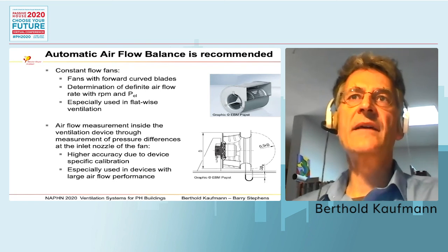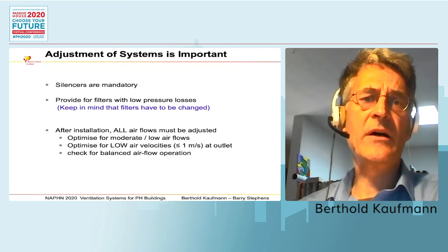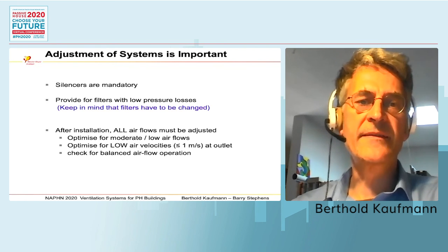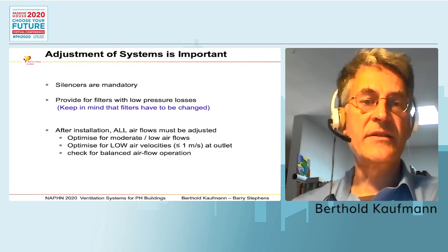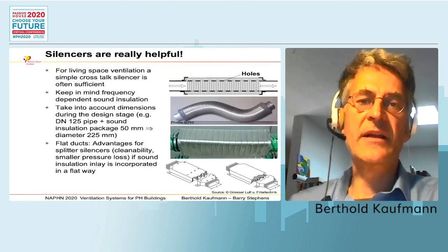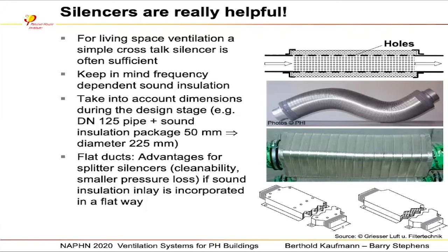Well, and now the last part is about adjustment. Just a few hints about what we need: silencers, filters, and a check of the installation. First a remark, please: we do have to install silencers, as otherwise the noise level would be too much in the end. Silencers are a little bit costly, but it's worthwhile. Even if we have an air conditioning system, your client will be happy afterwards not to hear anything from the ventilation system.